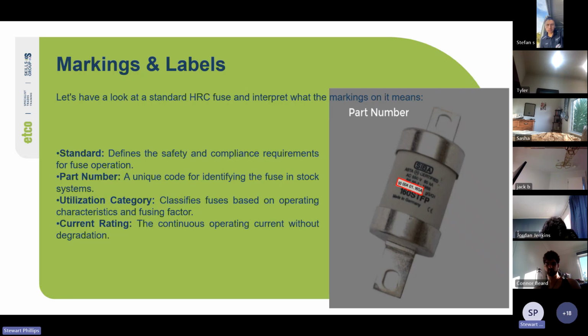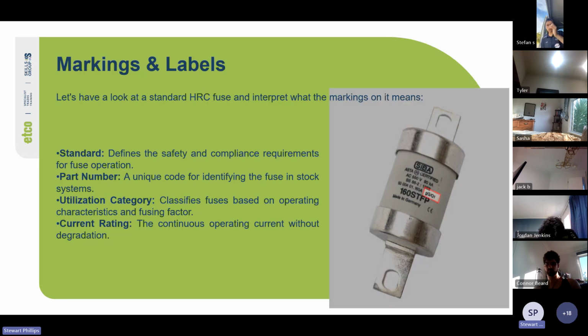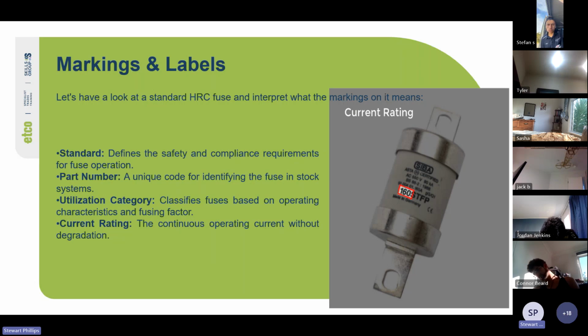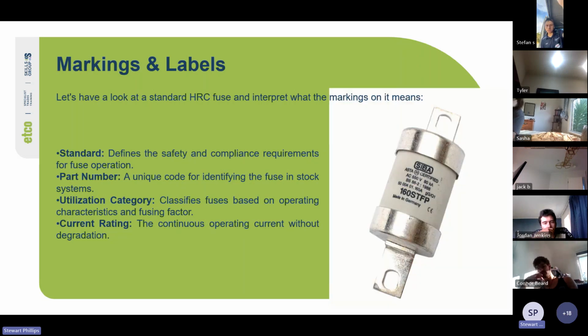The other thing to know about HRC fuses, they don't like being exposed to outside weather. So if you have a meter box that has a cracked fuse holder and the meter box door doesn't shut properly, it's probably a good idea to replace the hinge and the latch on the door, as well as the fuse holder and the fuse as well, because you cannot guarantee that it's going to act correctly.